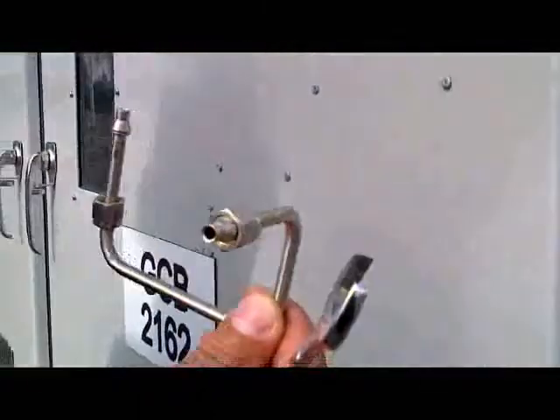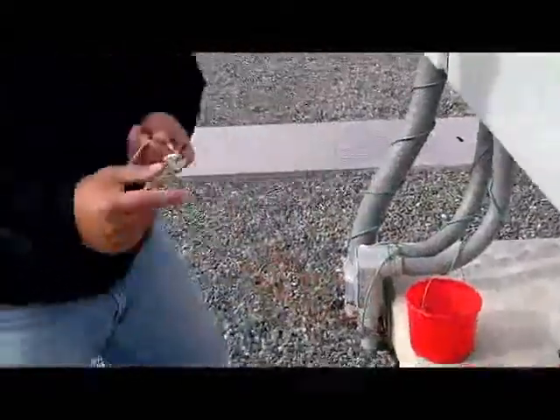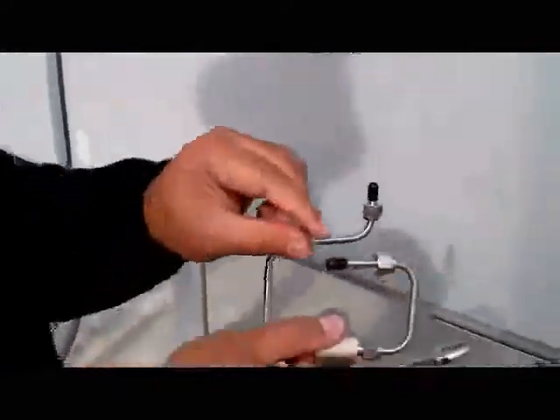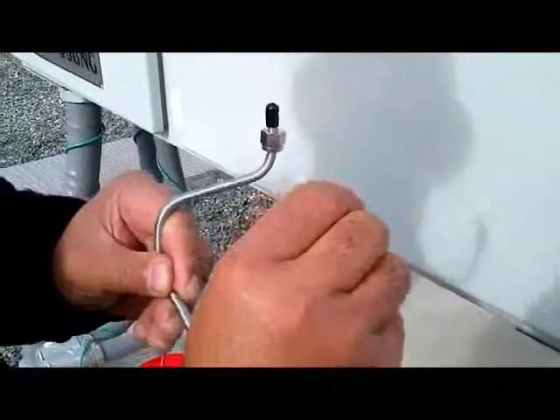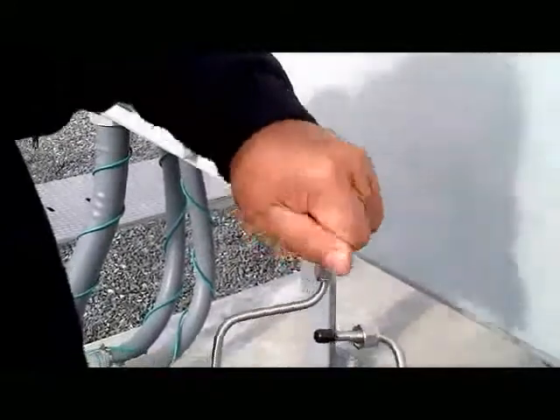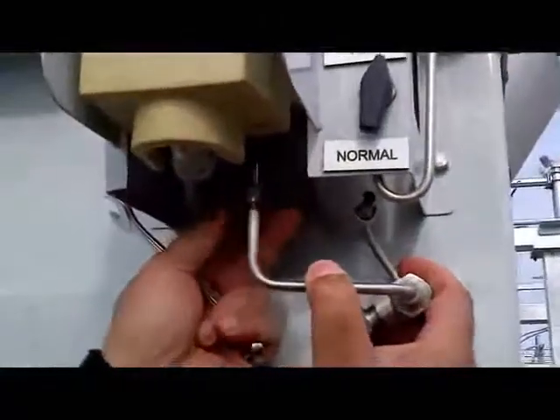And these are the existing fittings. So we're going to retrofit the sensor with our fittings that we already redesigned. And this is it. Turn it around, and make sure you don't remove this black fitting here, the tubing here that holds the fittings from slipping through. First you have to remove this one. It's kind of hard, you have to turn it to loosen it up and it comes out. Make sure this thing is loose and don't drop any ferrule.